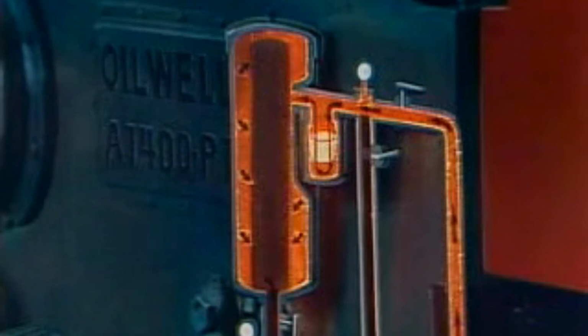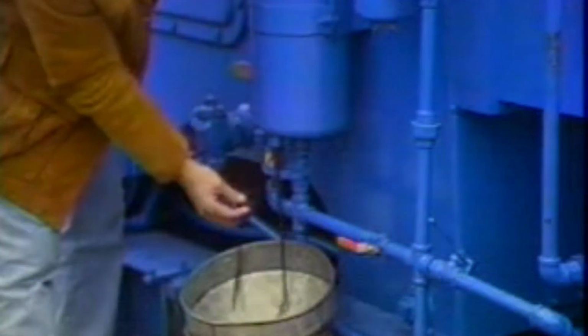If the pressure at the inlet to the filters has increased to 15 pounds per square inch above the pressure at the filter outlet, this indicates the oil isn't flowing well through the filter. Most likely the filter element's dirty, so change it. You can change the element in this cartridge-type filter while the pump is operating if you need to. There are valves provided to let you bypass the oil filters while you're working on them. Remember to route the lubricant back through the filters once you're finished.